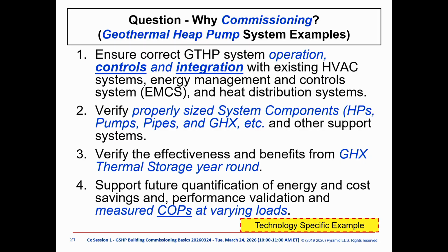Verify properly sized system components—heat pumps, pumps, pipes, the ground heat exchanger. You don't want to oversize too much, and that's a problem we have. We say we have poor project economics because the project has been oversized and breaks the bank. But guess what—you can have a smaller project and maybe inject some propane sometimes during extreme cold, like 20 below. This way you can save a ton of money on the ground heat exchanger if you're willing to cover like 3% of the time when it's 10 or 20 below in New York State. So you can do a lot of upfront savings this way.